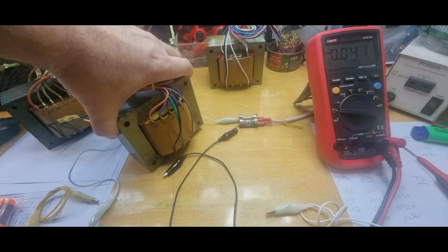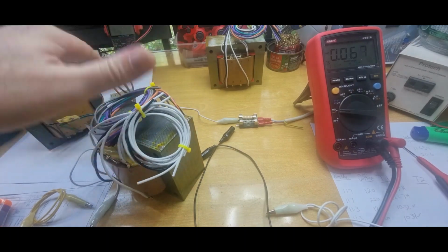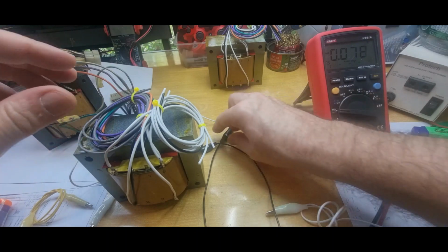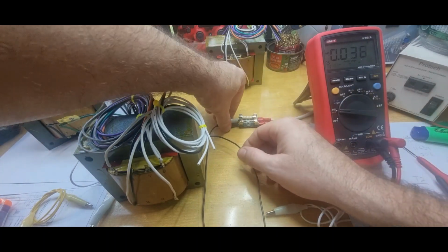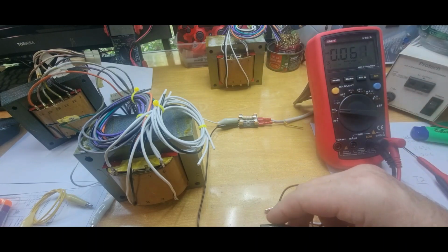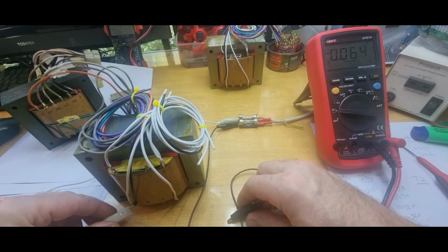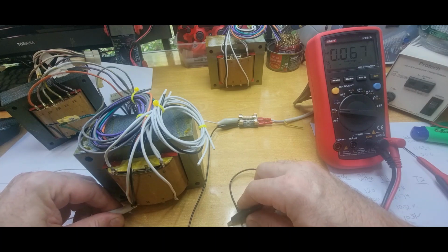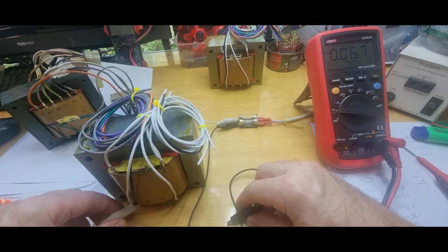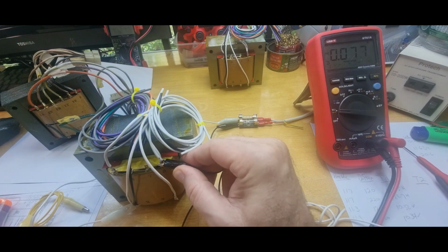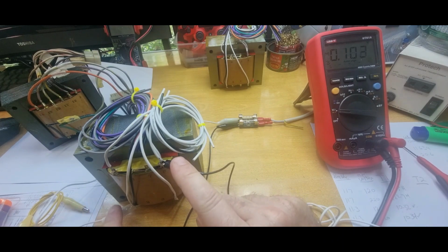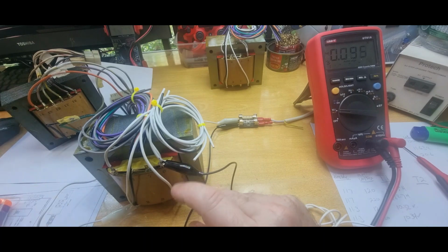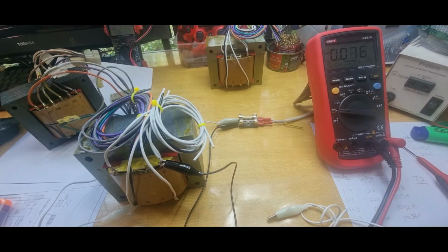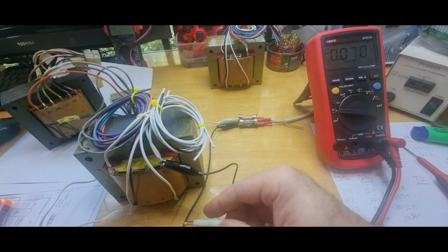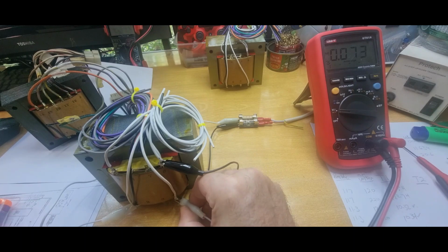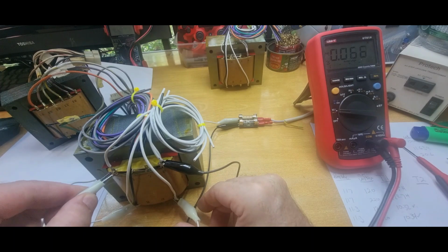All right, let's get this guy back up here, 1 through 8. Let's get the primary side up here, we'll wire him in. We're going to power both windings, and we're already on 220, so we're just going to run there. That's the beginning of the first winding, that's the end of the second winding, and then where's my other jumper? This is the white one, and this is the end of the first winding, and we're going to take it to the beginning of the second winding.